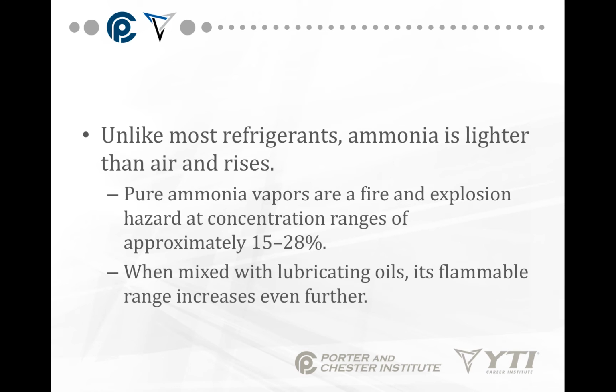You have to think about a couple of things with refrigerants. Unlike most refrigerants, ammonia is lighter than air and rises. Pure ammonia vapors are fire and explosion hazards at higher concentrations of approximately 15 to 28%. When mixed with lubricating oils, its flammability increases even further.